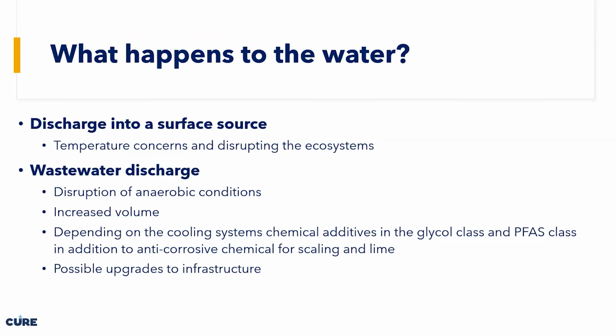But likely there's going to be a temperature change and additives to that water. When we're looking at a data center, they're looking at anti-corrosive chemicals, and typically some of the refrigerants have glycol class additives or certain PFAS, the F class PFAS. Wastewater treatment plants aren't designed to pull those chemicals out of the system, and so they would likely need wastewater infrastructure upgrades in order to deal with those.